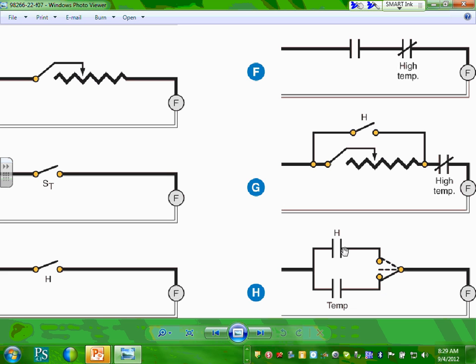So anyway, all these are options for you to control that thermostat. Please read through them. Typically, you have a high temperature or temperature control on these fans, and let it run based on the temperature that you set. Any comments, any questions? Yes, sir. On that one we were doing earlier, that had the temperature control. Yeah, the exhaust fan that you have in our lab will have a temperature control switch on it. If the temperature goes above a certain value, say 95, 100, it starts exhausting. When the temperature goes below a certain value, it stops.